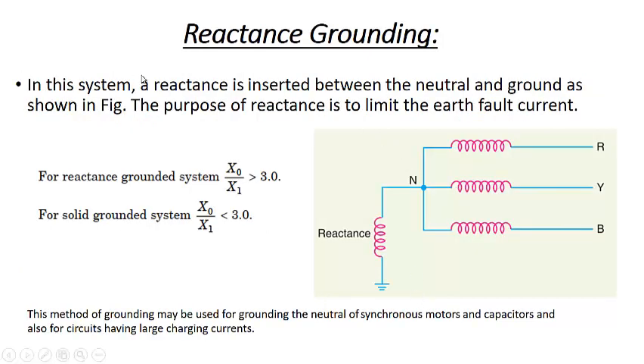So to eliminate that power loss, we may go for reactance grounding. In this case, the neutral is connected to the ground through a reactance. And there is a particular relation for a reactance grounding system: if X0 by X1 is greater than 3, it is reactance grounded, and for a solidly grounded system X0 by X1 is less than 3. This X0 is known as zero sequence reactance, and it is, we can say, a direct reflection of the reactance of the neutral. X1 is the positive sequence reactance, and we will discuss them in detail in the power system second course. For the time being, we can say that this X0 is the reactance of the neutral. So when X0 by X1 is greater than 3, that means this reactance has a good value, that means it's a reactance grounding. When X0 by X1 is less than 3, that means this X0 has a very small value. In that case, we can consider this to be a solidly grounded system.